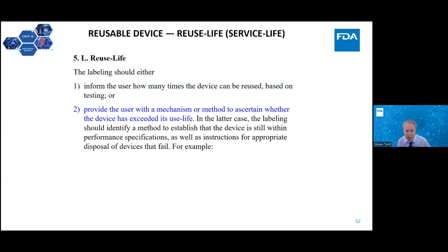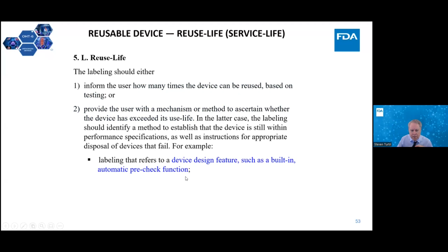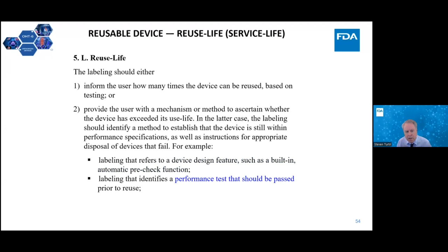Or, provide the user with a mechanism or method to ascertain the device has exceeded its use life. In the latter case, the labeling should identify a method to establish that the device is still within performance specifications, as well as instructions for appropriate disposal of devices that are not. Examples of these are labeling that refers to a device design feature, such as a built-in automatic pre-check function. It could be an electronic feature that is built in. There are so many different device types, and I work in orthopedics, so I don't see this very often, but it can be a very highly functional device, and there needs to be a pre-check to make sure that the performance is up to where it should be. Labeling provides performance tests that should be passed prior to use. This could be as simple as pulling the trigger on the handle and making sure that the jaws close at the other end, or it could be more complicated than that, but this is an example.